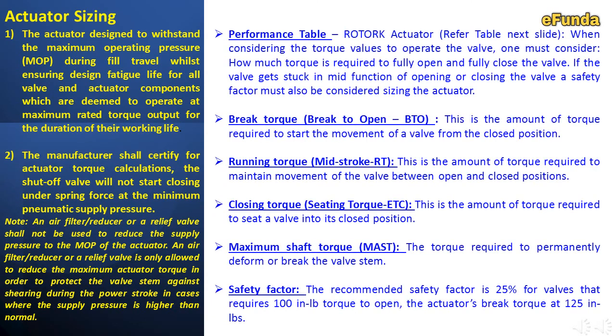While the actuator sizing performance table is a key factor, in this case we are referring to a rotork actuator for reference only. When considering the torque values to operate the valve, one should consider how much torque is required to fully open or fully close the valve. If the valve is stuck in between, mid-function of the opening or closing state of the valve, a safety factor is required to be considered while sizing the actuator.